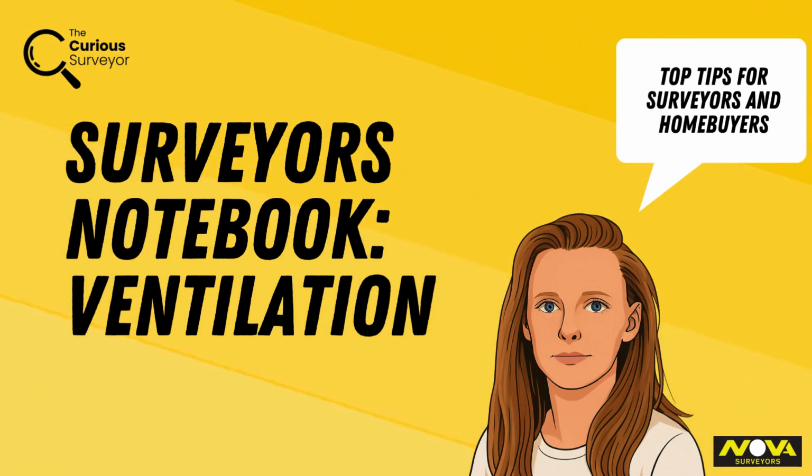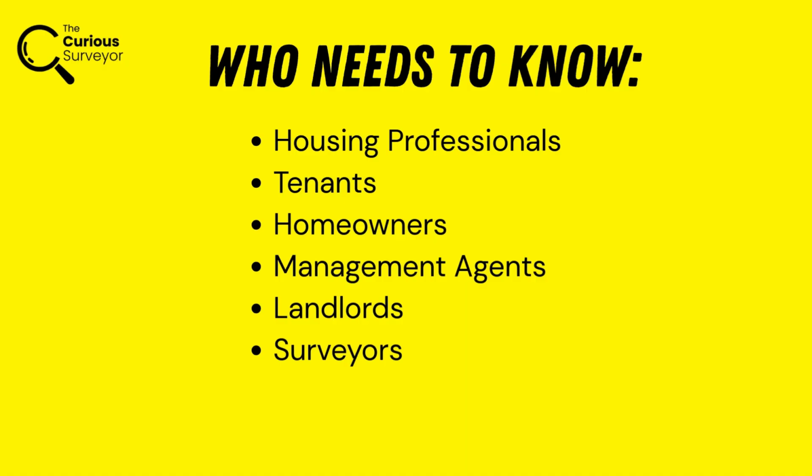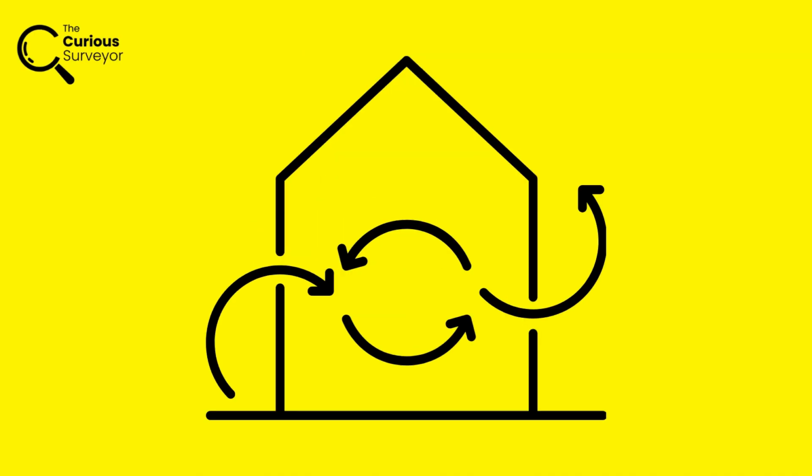If you look into the Awab Ishak case, the actual main defect within the property related to ventilation, partly in the sense that the extractor fan in the bathroom wasn't working, but also that there was no extractor fan in the kitchen and the window in the kitchen opened into the communal hallway. The bathroom didn't have a window at all. So I just wanted to talk you through some of the things that I found recently. Hopefully you'll find it useful.